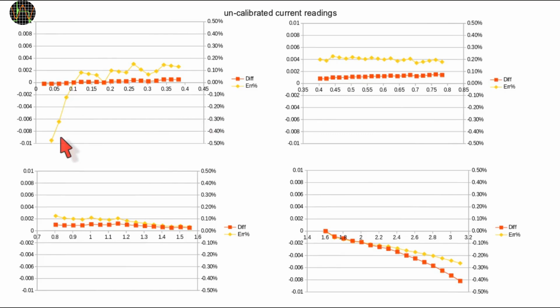As you can see, the difference values are quite close to zero even at low currents, but the error increases exponentially because the lower the value, one LSB difference makes proportionally a huge error. I explained this issue already in the last video for a bus voltage. So practically minded people might as well leave calibration alone, but that's not what we're here for.